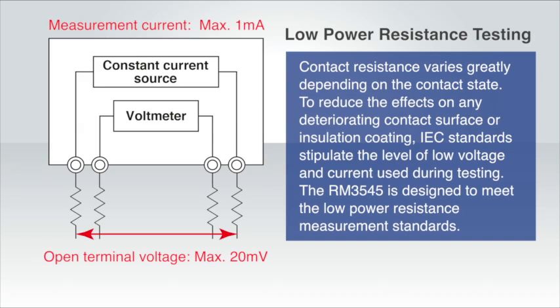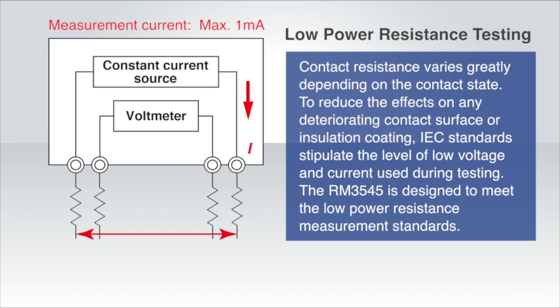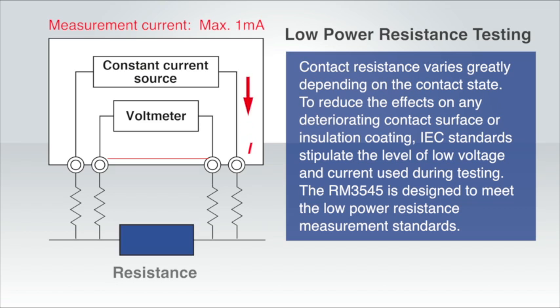The contact resistance of components used for signal contact varies greatly depending on the contact state. Because of this, the level of low voltage and current used for testing is stipulated by IEC standards so as to reduce the effects on any deteriorating contact surface or insulation coating. The RM3545 is designed to meet these low power resistance measurement standards.